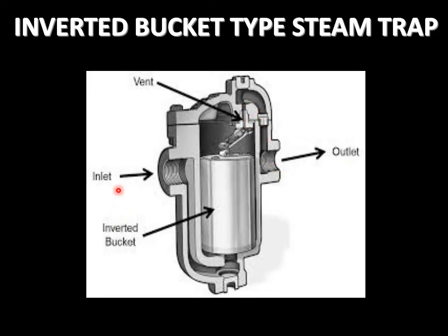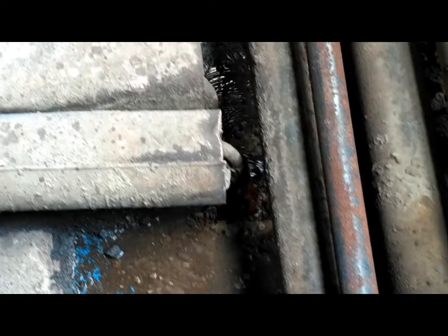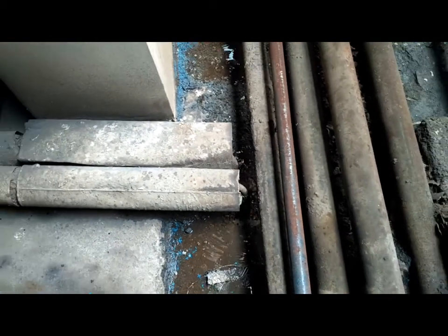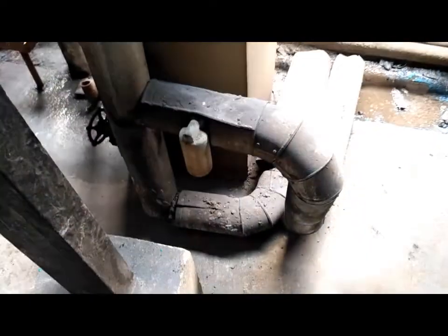Now when we have steam in majority inside this bucket or this steam trap, the bucket will become buoyant and move upwards, and this mechanism will close this port. So the flow of condensate outwards will be stopped. This is an example of an inverted bucket type steam trap.